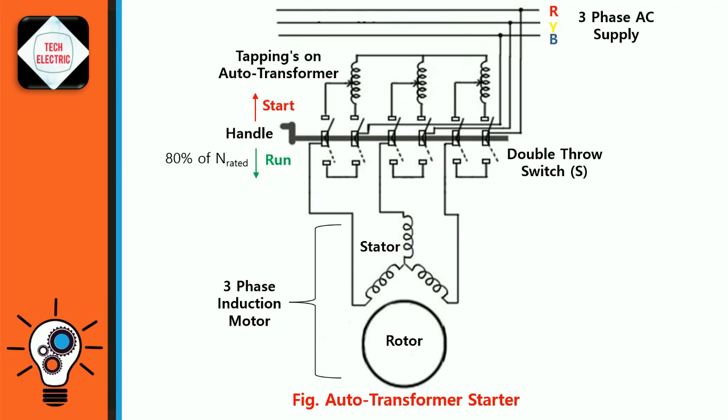The handle is held in the run position by the under-voltage relay. If the supply voltage fails or falls below a certain value, the handle is released and returns to the off position. Additionally, thermal overload relays are provided for the overload protection.